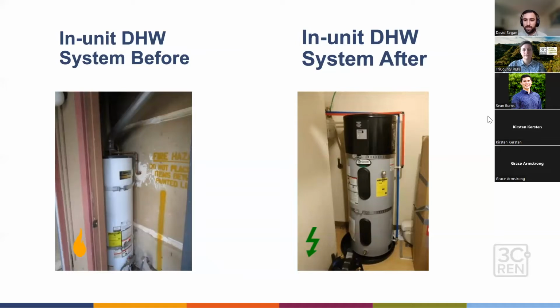So thinking about domestic hot water systems, there are several configurations that we see. One are residential systems or in-unit systems. On the left here, we have a natural gas tank type water heater, and on the right, we have a heat pump tank type water heater. We could replace the one on the left with the heat pump system on the right. This is a pretty straightforward upgrade, what we'd call plug and play. So not too much engineering design is needed to swap out a natural gas tank type water heater with the heat pump system. A couple considerations that we have with this swap is space.